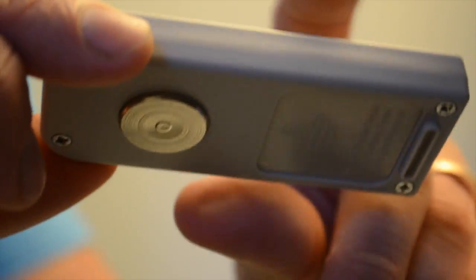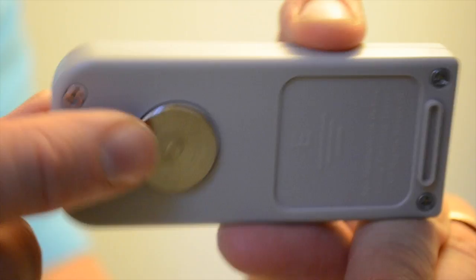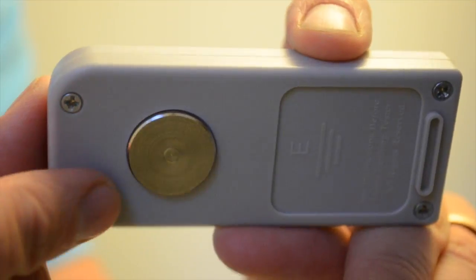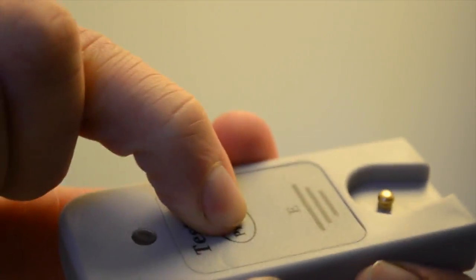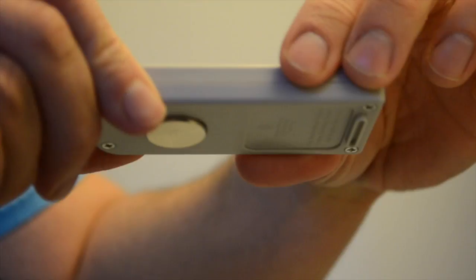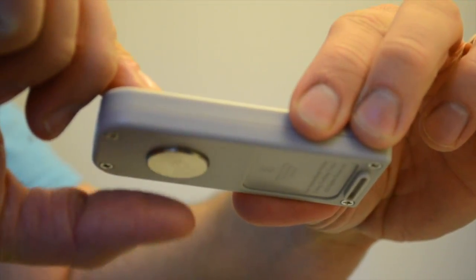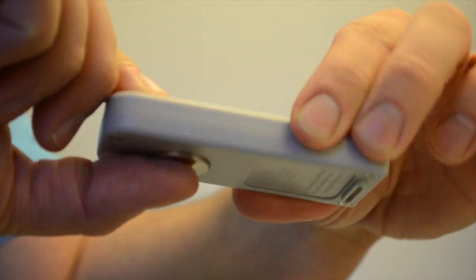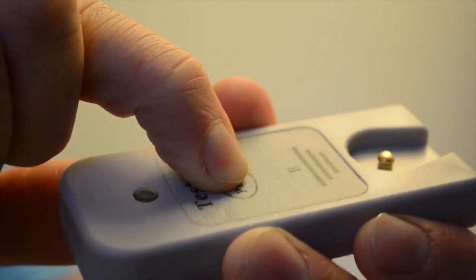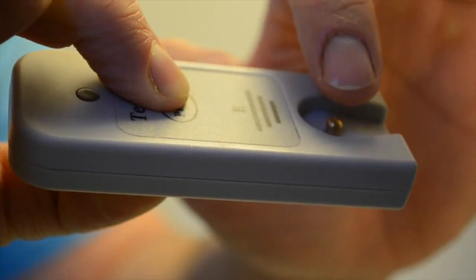First, test if the Smart Conductivity Tester has a charged battery by using your own conductive body to demonstrate that the tester is working. Place your thumb so it is firmly touching the metal surface of the battery on the underside of the tester. With your pointer finger on the same hand, press and hold the tester button down. The green light will flash once.